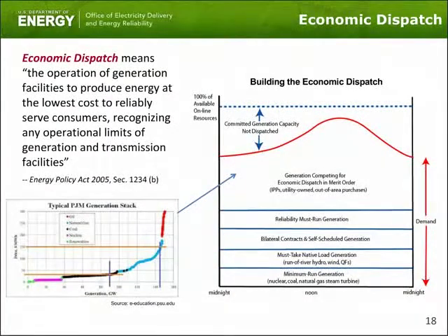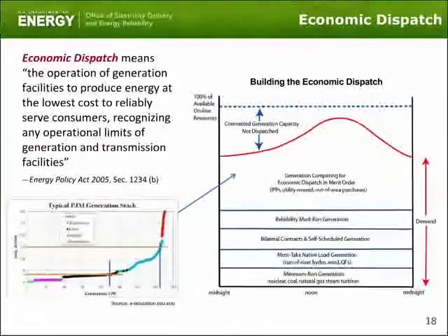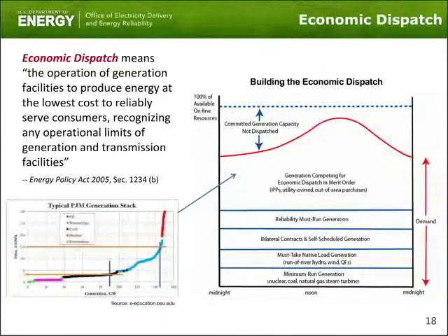These costs include capital costs, such as plant investment, as well as variable costs and fuel. If you have higher capital costs, historically things like a nuclear plant, you tended to want to run them a lot, and so they factored into what was called base load generation, which is usually pretty flat. And those that had increased variable costs but low capital costs, which was historically things like natural gas, would often tend to be more for peaking purposes. But now with fuel cost changes and changing economics, natural gas is appearing in more of the base load and intermediate as well. Slide 19, please.